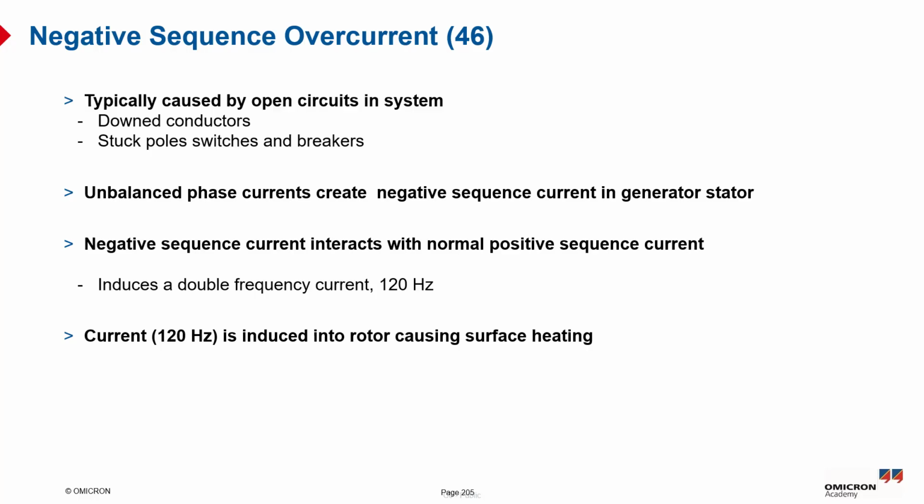Over time, this surface heating can cause significant thermal stress and potential damage to the rotor, making it essential to detect and limit negative sequence currents to protect the generator's mechanical integrity.